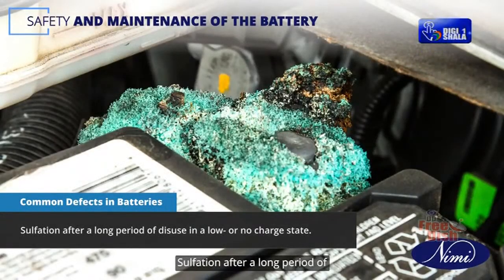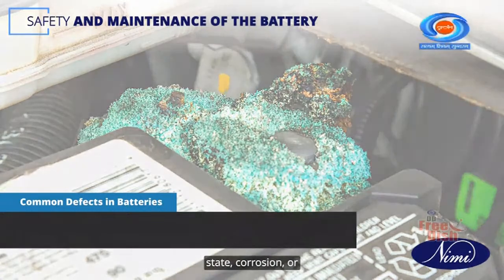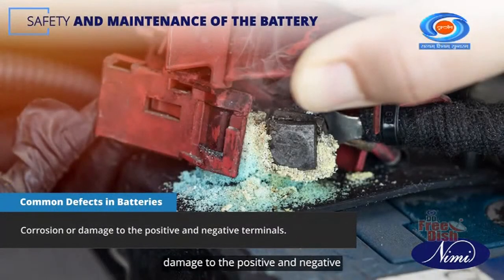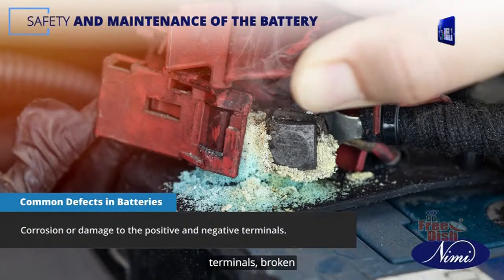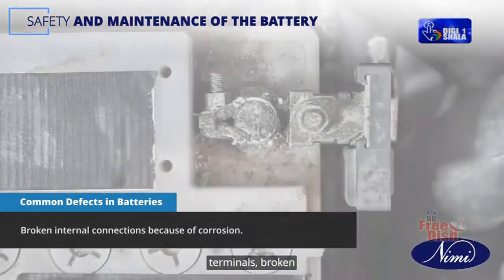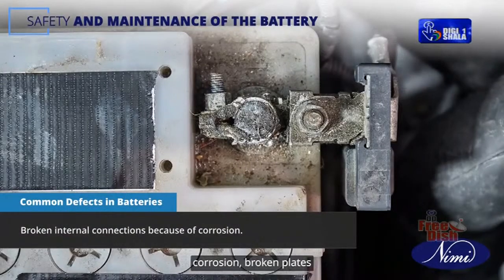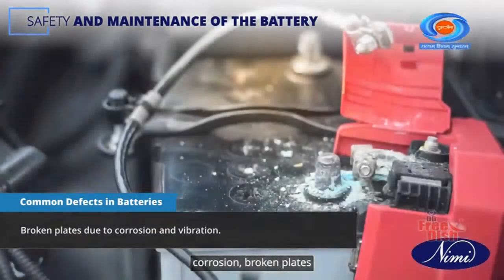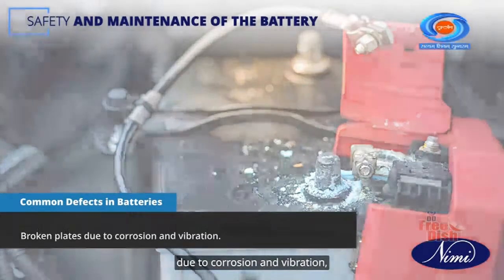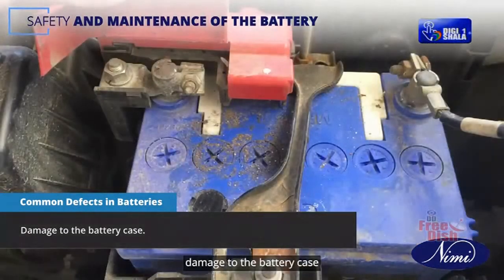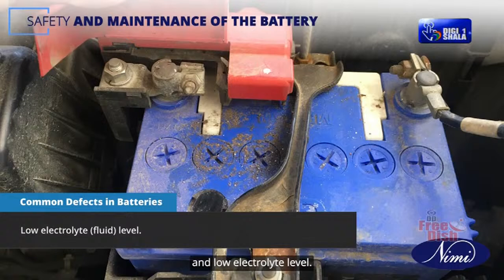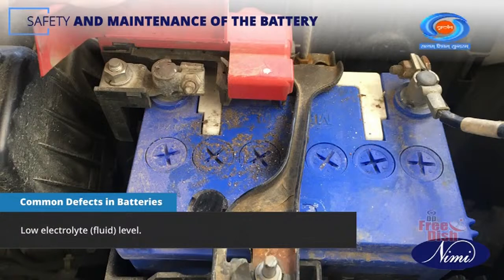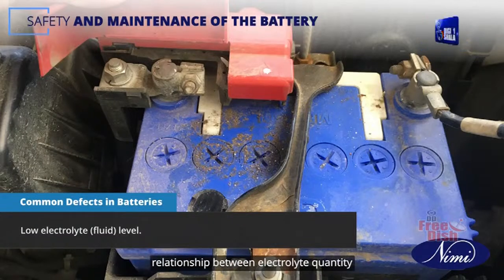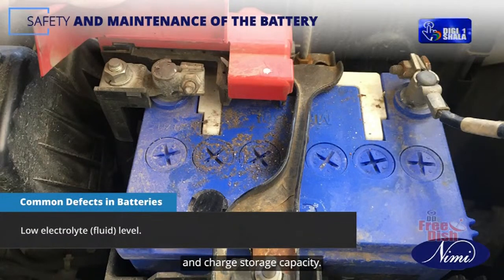sulfation after a long period of disuse in a low or no charge state, corrosion or damage to the positive and negative terminals, broken internal connections because of corrosion, broken plates due to corrosion and vibration, damage to the battery case, and low electrolyte level. In the next section, you will see the relationship between electrolyte quantity and charge storage capacity.